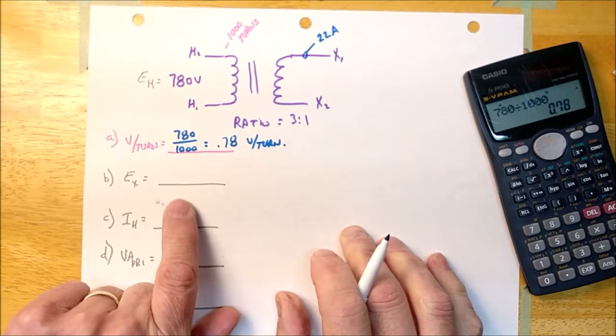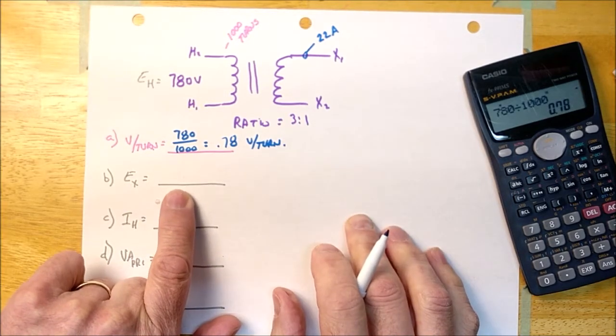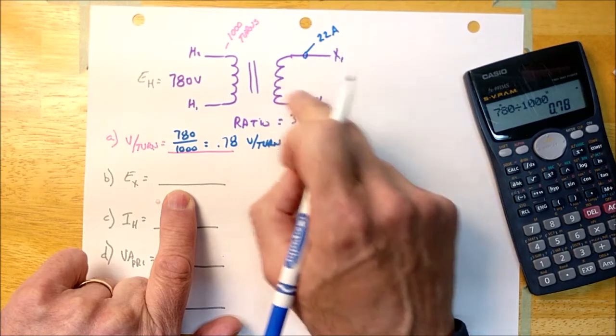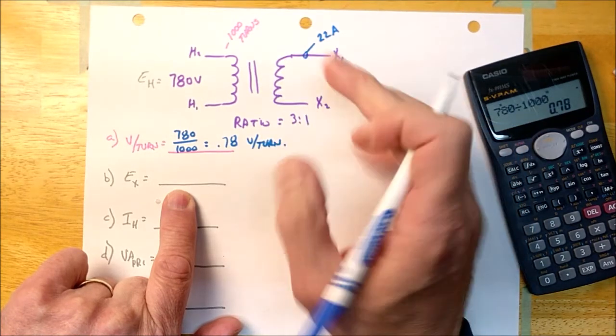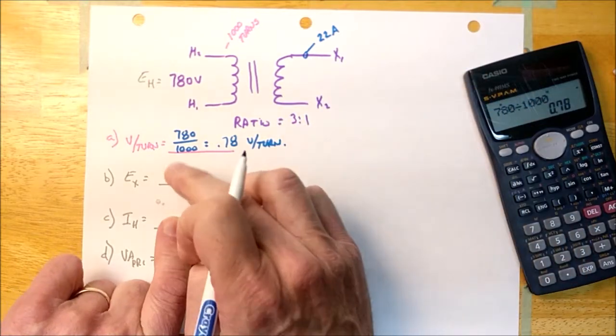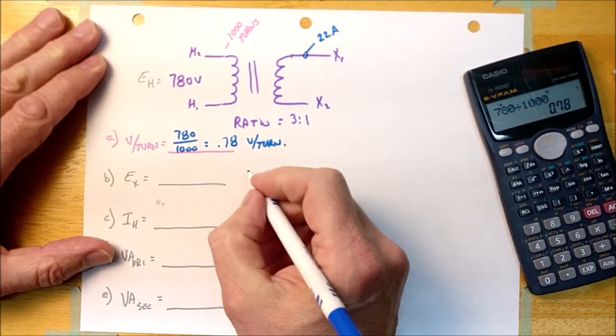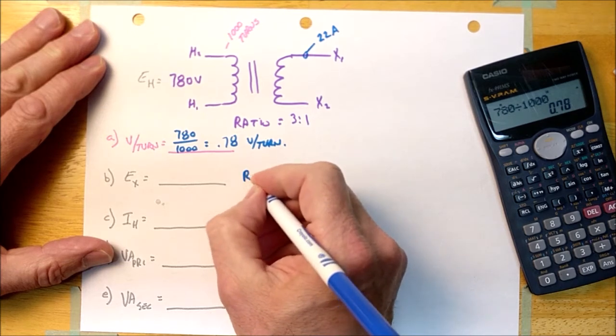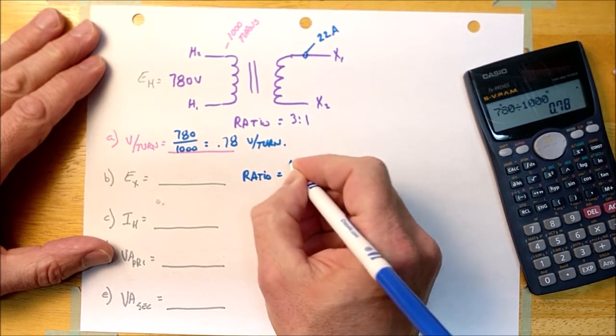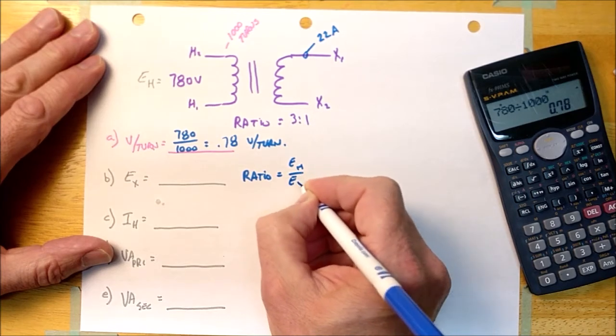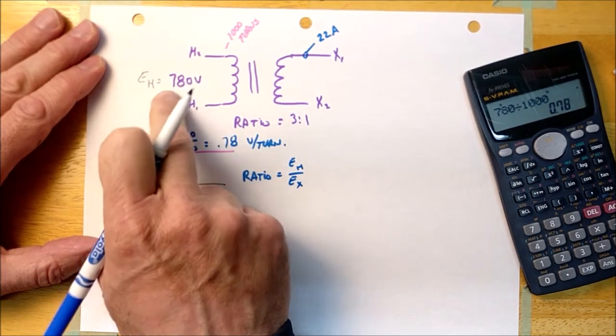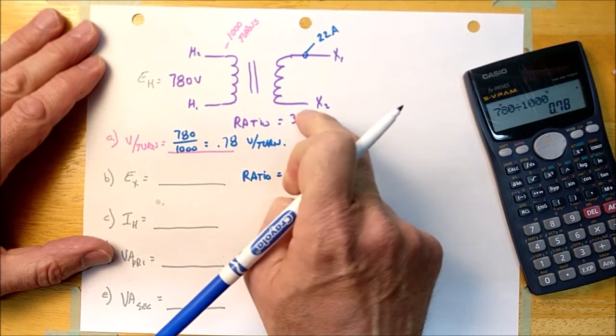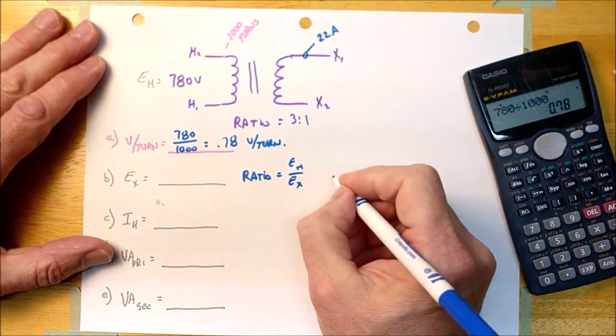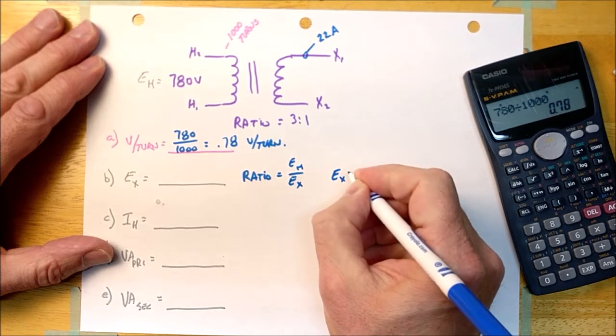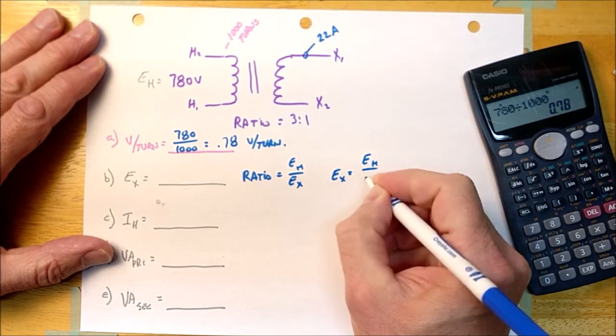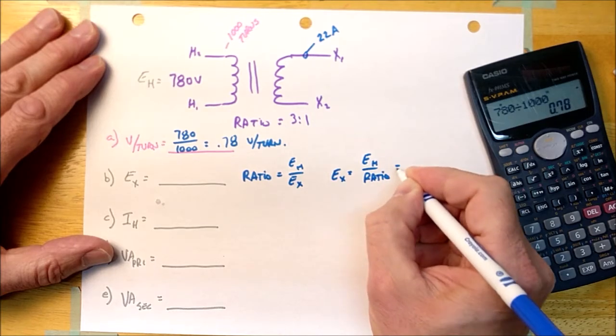Now it wants to know, what is the voltage on the secondary side? I don't know how many turns are on the secondary side, guys, and I could figure it out using the ratio, but I'm not going to bother. I'm going to calculate EX using this formula right here. The ratio is going to be EH over EX, okay? And I know EH, I know the ratio, and I want to calculate EX. So if I transpose that, EX is going to be EH over the ratio, if it's transposed correctly.